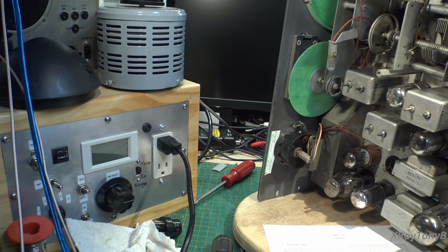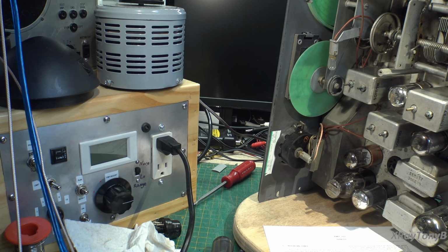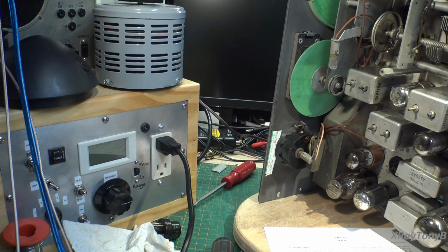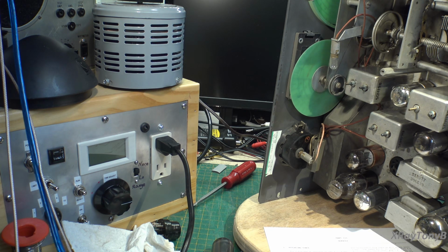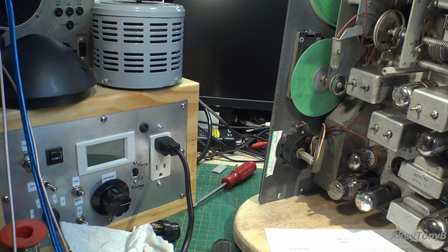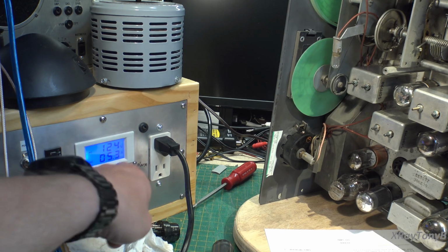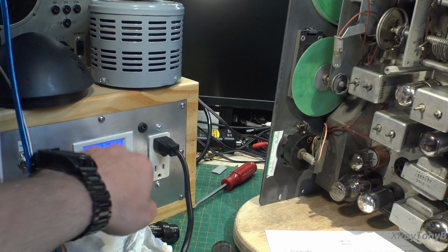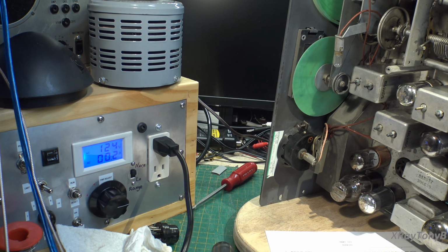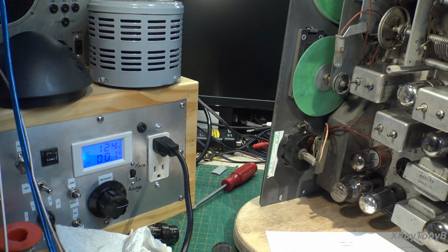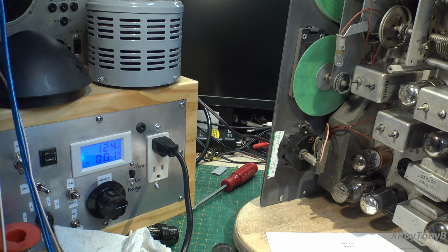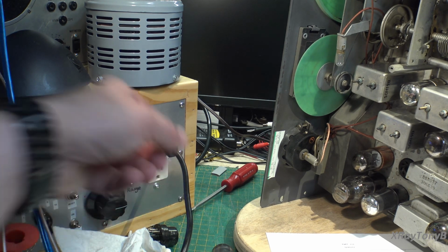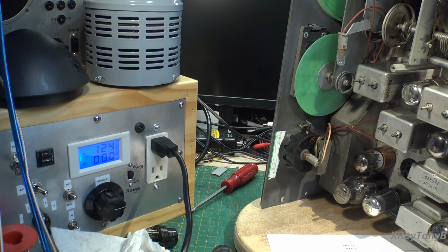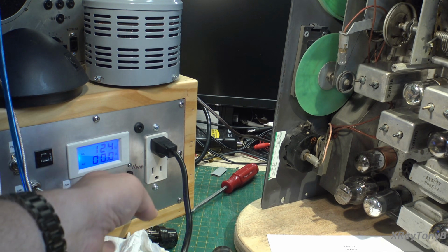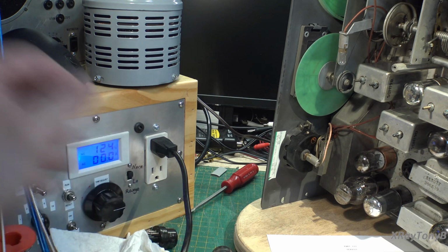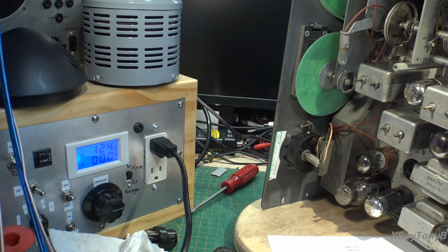I thought it was a fluke. Working with it again, all of a sudden it trips again. So something's not right. I reset it, and I noticed the current, which normally stayed right under 1 amp and around 800 to 900 milliamps when running, started creeping up over 1 amp to about 1.1 amp, which was right around our trip point, and it would trip.